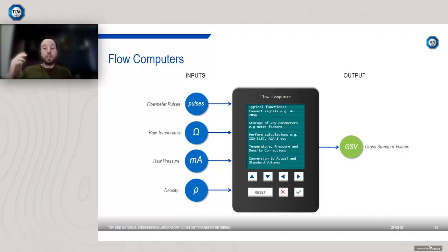So if you need to report gross standard volume, the flow computer is usually going to do that for you. What's really important is the flow computer needs to be audited on a regular basis because you could spend all the money in the world in a really sophisticated metering system, but if there's an error in the flow computer, someone enters something incorrectly, it's going to mess up the measurement results. So it's important these are audited and checked on a regular basis.